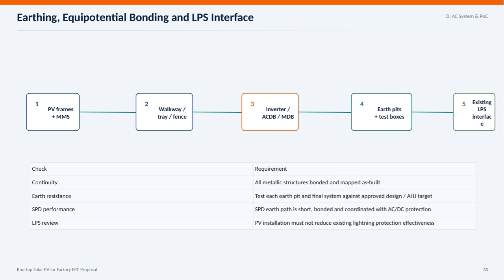Surge protection device performance is another vital point. The SPD earth path needs to be short and well bonded, coordinating effectively with the AC and DC protection systems to manage any surges. Lastly, the lightning protection system itself must be reviewed to confirm that the PV installation does not compromise its existing effectiveness. These checks collectively ensure a safe, compliant, and reliable solar power installation integrated with the factory's electrical and protective infrastructure.